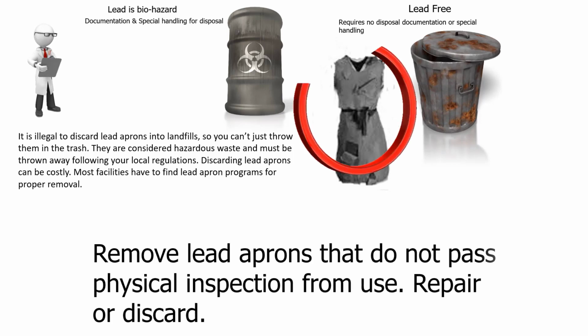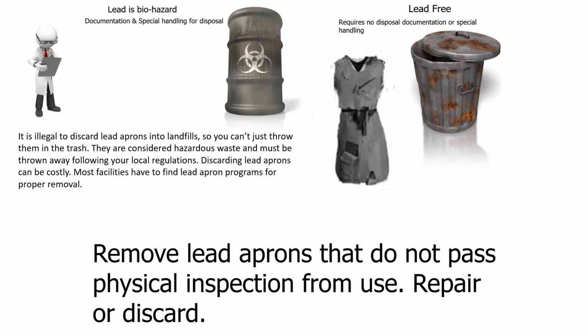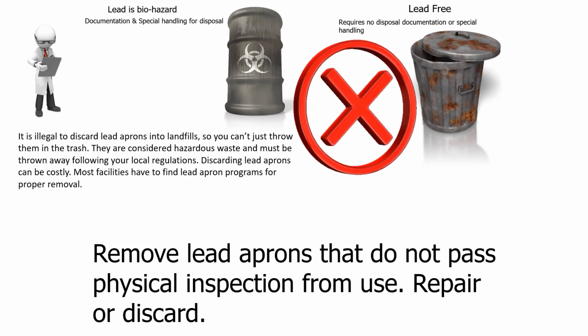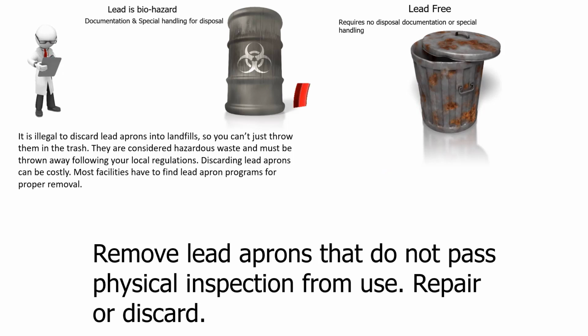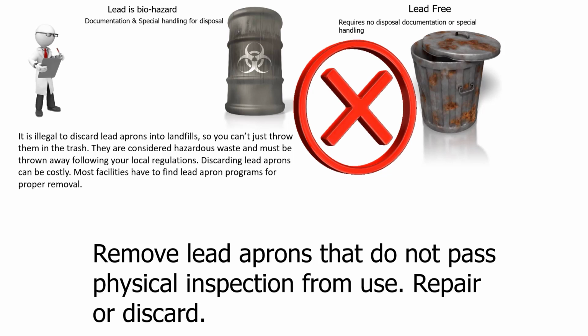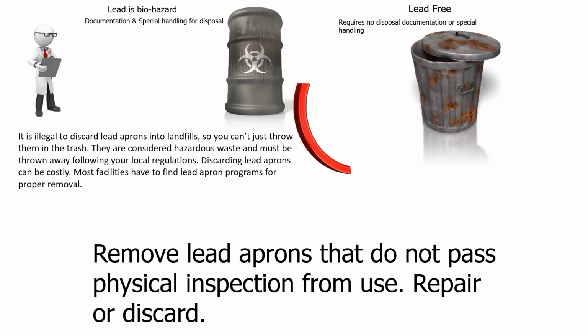Remove lead aprons that do not pass physical inspection from use. Then you may either have the apron repaired or you may discard it. When you discard the lead apron, it makes a difference whether it is a lead apron, which is a toxic material, or a non-lead apron, which is a non-toxic material. Lead is a biohazard, and documentation is essential on the disposal of lead aprons.